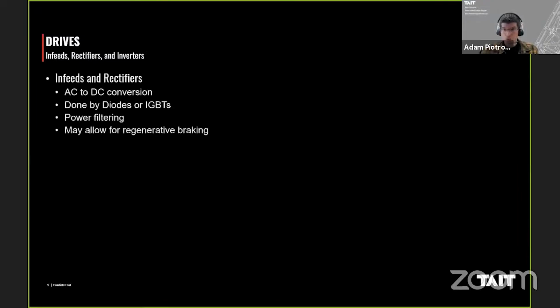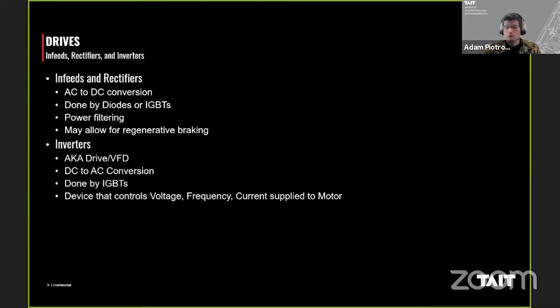And so there are two big pieces that make up a drive system. You'll have an in-feed and rectifiers, and you'll have inverters. The way that a drive, or the control system, works in order to produce the different voltages and frequencies that it needs to spin a motor is by converting that incoming AC from the utility into DC. That's done by the rectifier, either by diodes or insulated gate bipolar transistors. It does power filtering, and it may allow for regenerative braking if necessary.